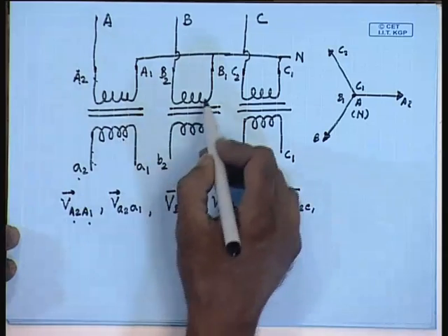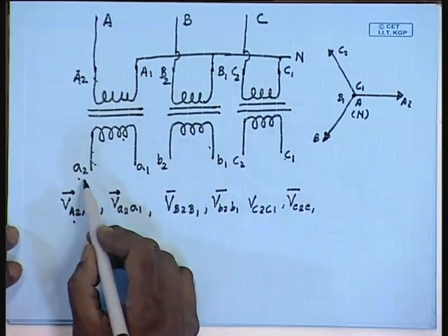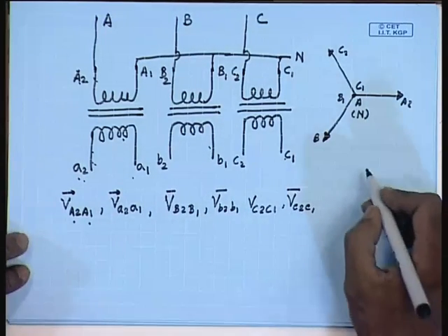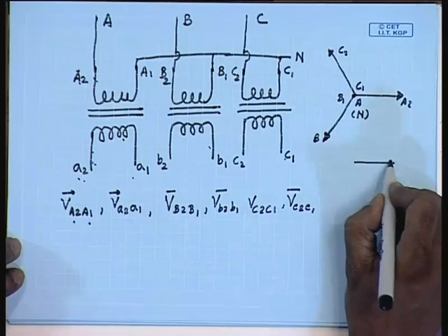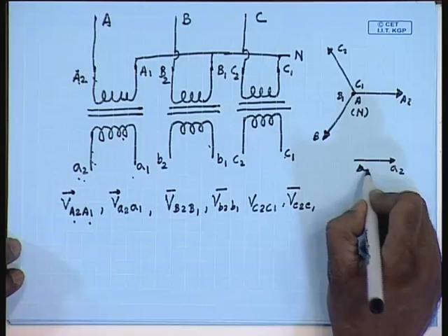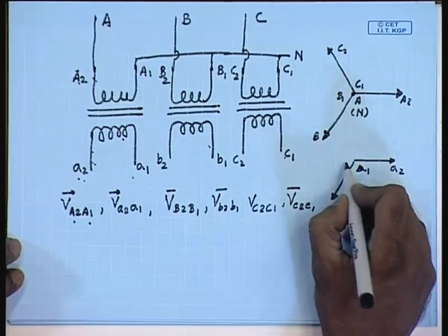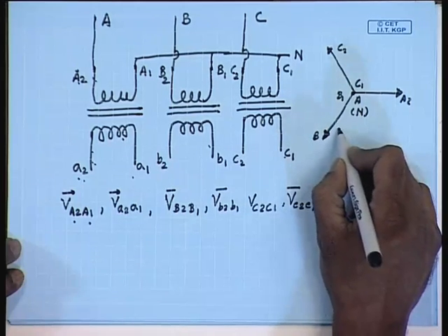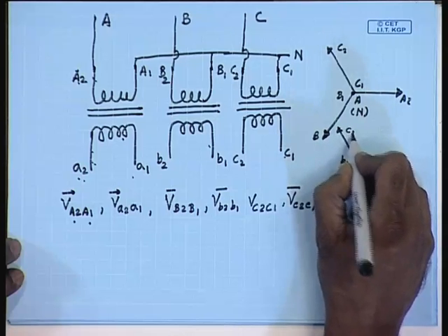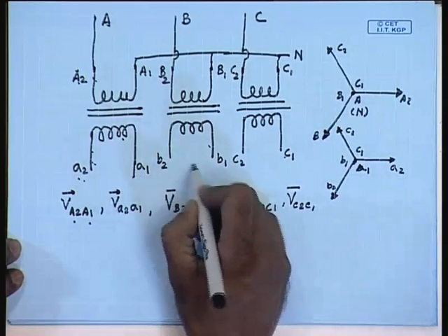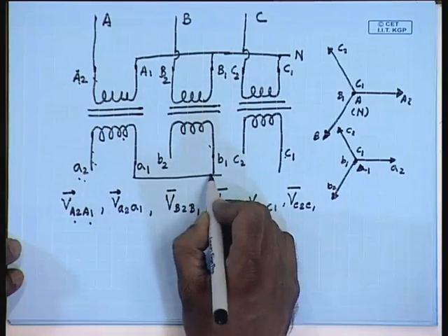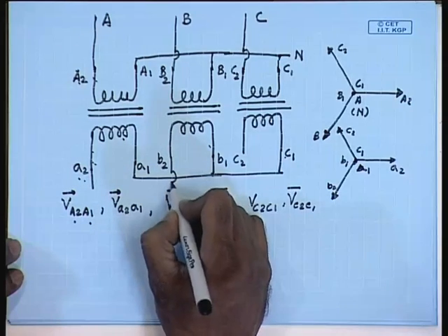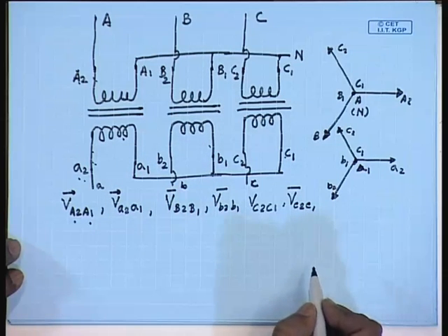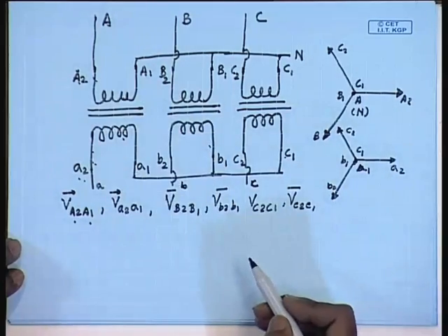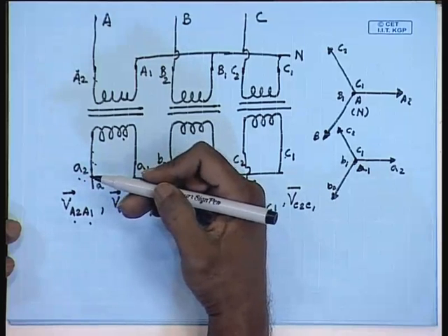Now, since these transformers operate independent of each other, the voltages V_a2a1, V_b2b1 and V_c2c1 will be cophasor to their respective high voltage phase voltages. So, the voltage V_a2a1 will be this, V_b2b1 will be this, and V_c2c1 will be this. Hence, we can connect the 1 terminals on the low voltage side also in a star and obtain the output voltage on the 2 terminals. That way, the phase voltage and the line voltage on the high voltage side and low voltage side will be cophasor.